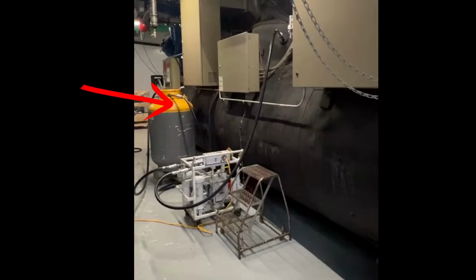We'll recover this until all the liquid is gone. That is the ultimate goal. We want to get all the liquid out via this push-pull and in here, which there's two ways of determining that. Or I guess technically three. One, you could have a sight glass here on the liquid line coming into the tank. When that sight glass goes to, I guess just vapor, it's no longer liquid flowing through there, would be the simplest way to say that. Then you've got the liquid refrigerant out of the evaporator. That's where the refrigerant's going to stack on most of these chillers. It's going to all be in the evaporator side.